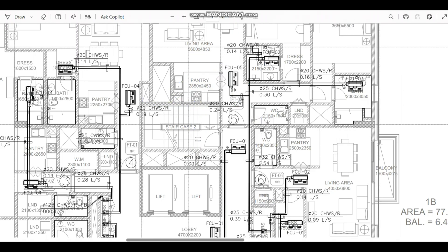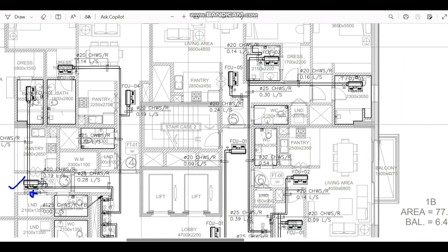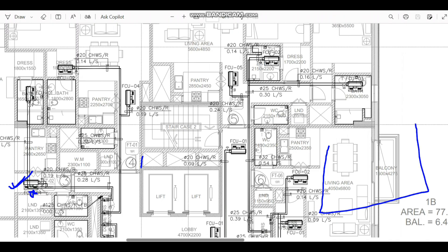Coming to the next point: FCU installation clearance. For example, this FCU has been installed with very limited space in the back side. Normally, the FCU has a filter that needs to be cleaned regularly, requiring us to open the access panel in the ceiling. When space is very limited and you have no other option but to place the FCU in a corner, the manufacturer recommends a minimum distance of 500 to 600mm behind the FCU from the wall.